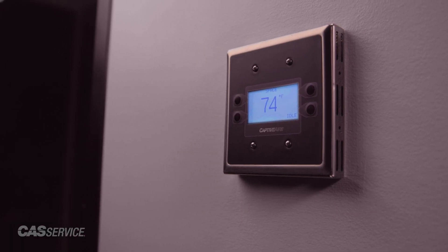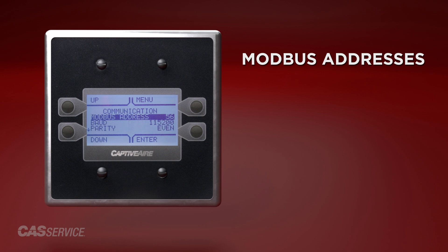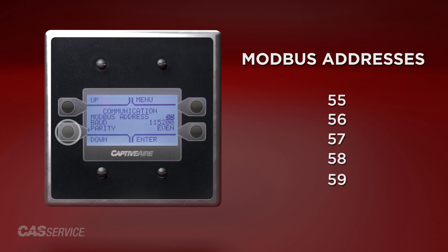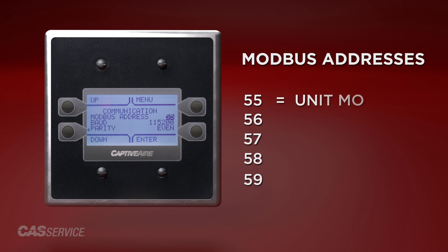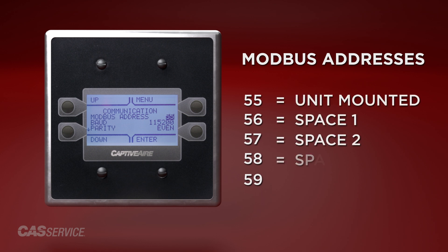The HMI Modbus addresses will be as follows: 55, 56, 57, 58, and 59, where 55 is always the unit-mounted HMI, with each additional one being a space HMI if configured as such. At a minimum, the unit will always have one unit-mounted HMI addressed as 55.